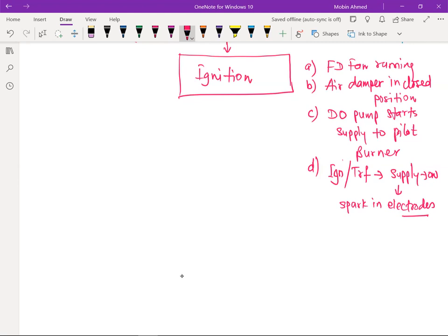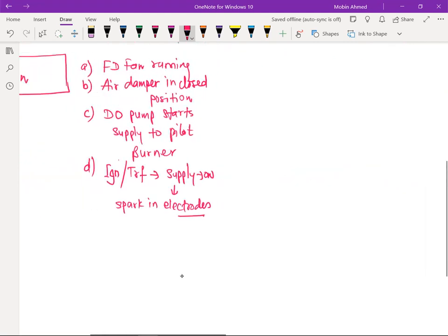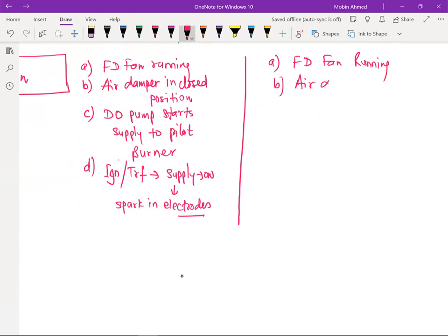Okay. This is going to happen when we are going to have the pilot burner. If the pilot burner is not there, then what will happen? Same thing is going to be there. FD fan is going to run continuously. Air damper is going to come to the closed position. In servo motor type also it is going to come in the closed position. Here the DO pump is not going to start.